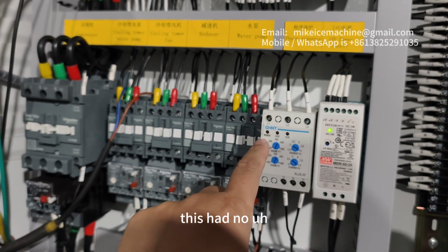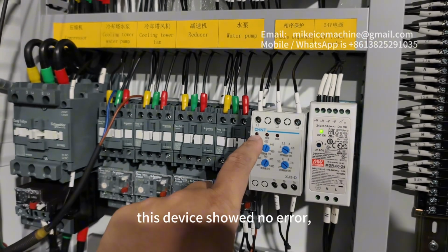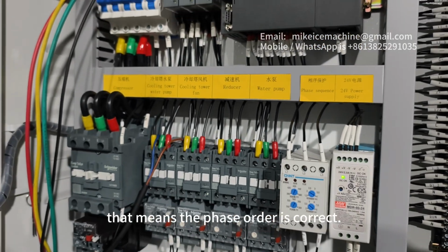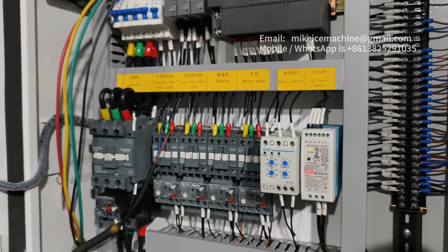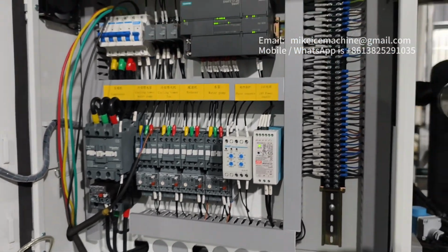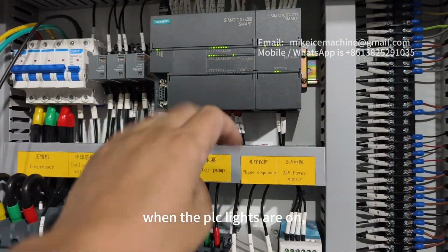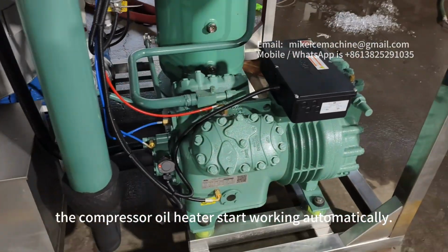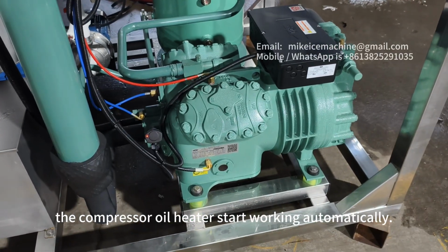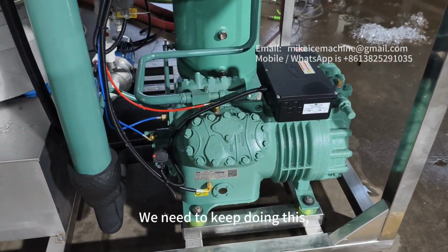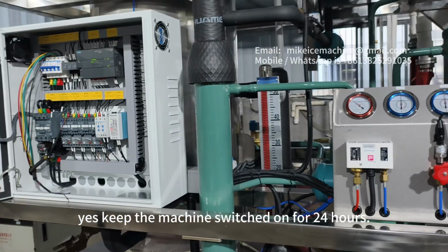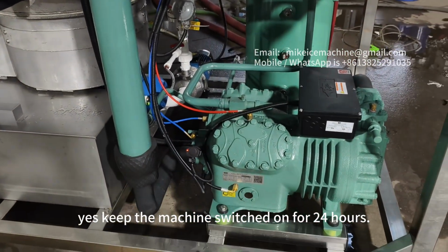When we see the lights on the PLC and the device shows no error, that means the phase order is correct. So when the PLC lights are on, the compressor oil heater starts working. We need to keep doing this. Yes, keep the machine switched on for 24 hours.